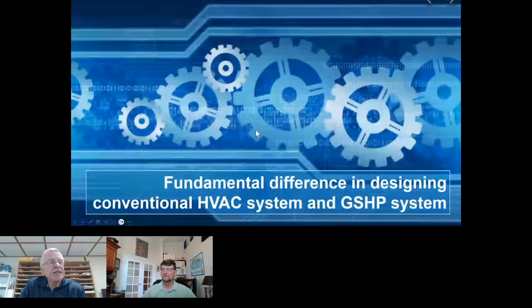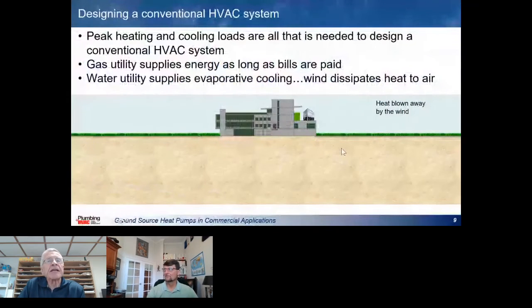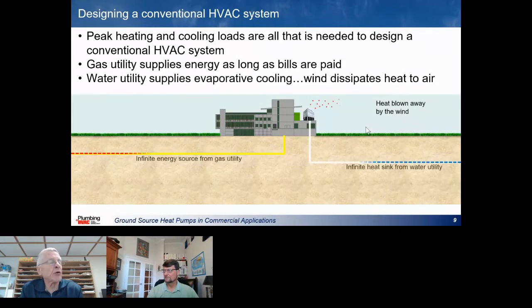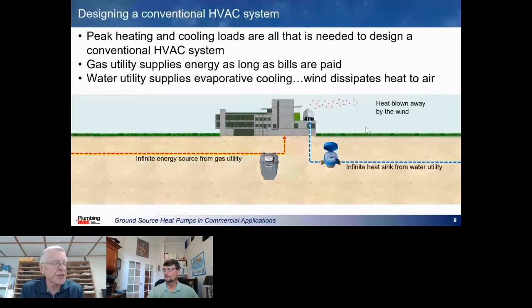So I'd mentioned some of the differences between designing a conventional system versus a ground source heat pump system. There are some very, very fundamental differences. If you're connected to a gas pipeline or an electric grid or an oil delivery service, you've got basically an infinite source of energy. As long as you're paying the utility or the delivery service, you've got energy. Doesn't matter how much you're using. Doesn't matter how much you're running that boiler or furnace. Somebody is going to shove energy down that pipeline.